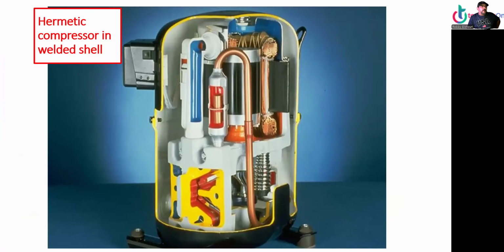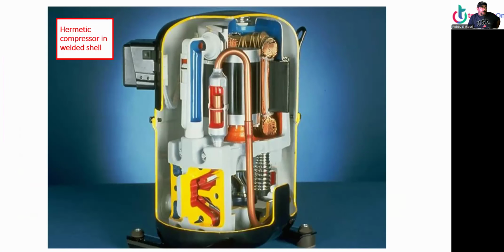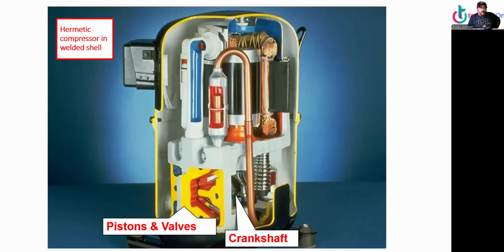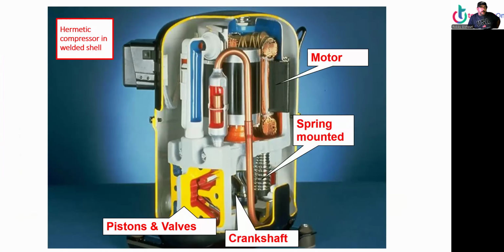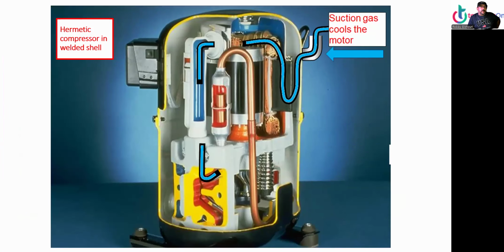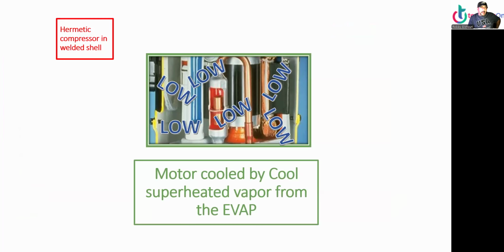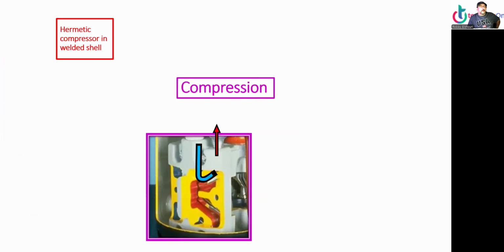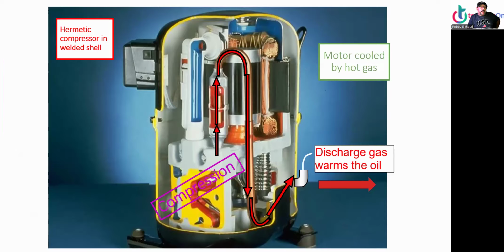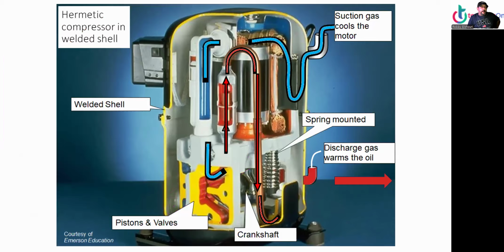Now, hermetic is welded in a case, welded. Pistons and valve there at the bottom, this one, the crankshaft, spring mount, the motor, suction goes in, the whole body is cooled by the suction line. And then the motor is cooled by superheated vapor from the evaporator, compression, and discharge. You see the discharge going up and down. It's bent down on purpose because of too much vibration, so it doesn't break. Alrighty, next.